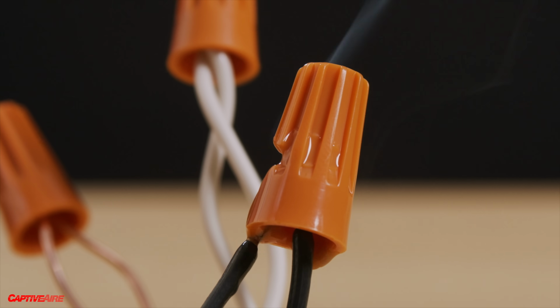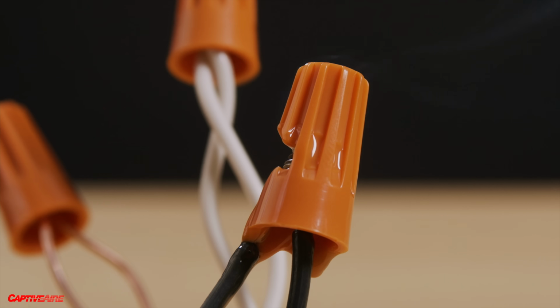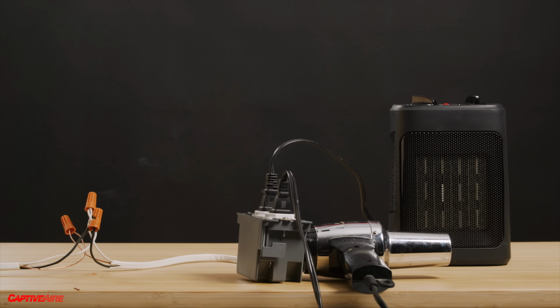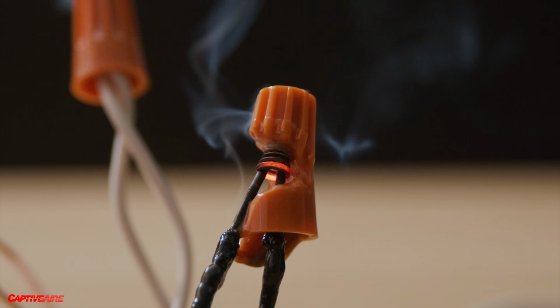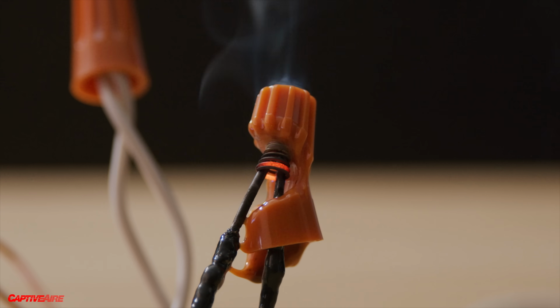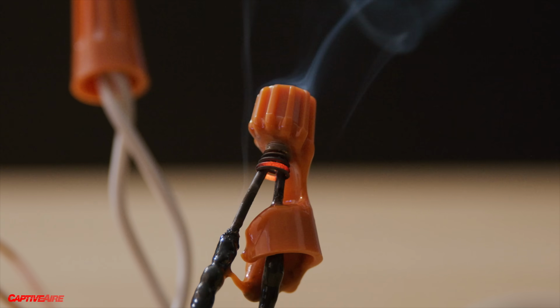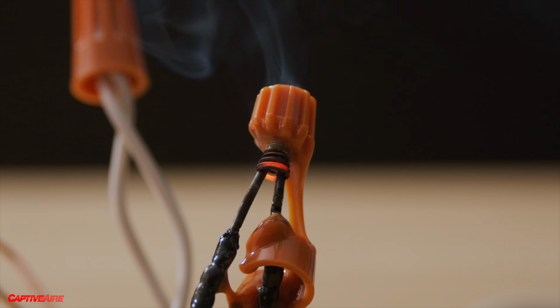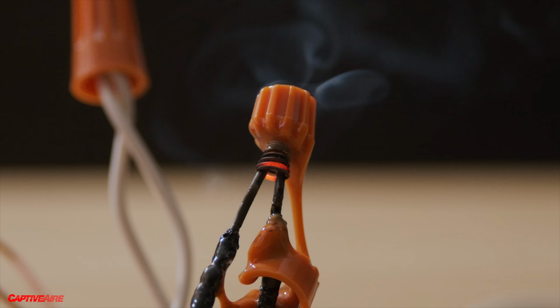The excess resistance is generating heat, so much heat in fact that it's even melting the insulation. The appliances of course continue to run and eventually this connection starts to glow from the heat. You can imagine that, even if this happened inside an electrical enclosure, the potential for fire is still real.